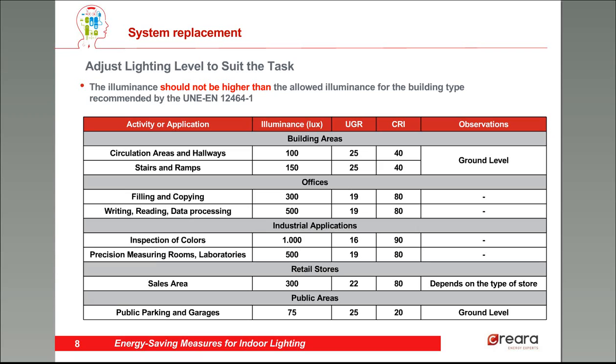Lighting requirements are different depending on the room and the task we are doing. As we can see in this table, the recommended illuminance in working spaces is around 500 lux, while in hallways it's only 100. This also happens with CRI — the color rendering index, which is the quality indicator for our capacity to see different colors. We don't need the same quality or the same quantity in every room, in every application. There is another indicator in the table headed with the letters UGR, the unified glare rating, which we'll see in the next slide.